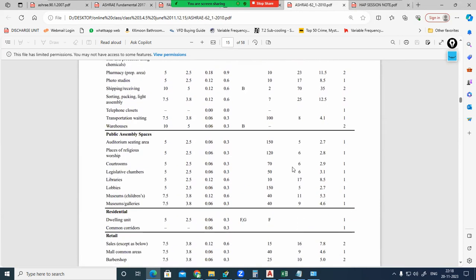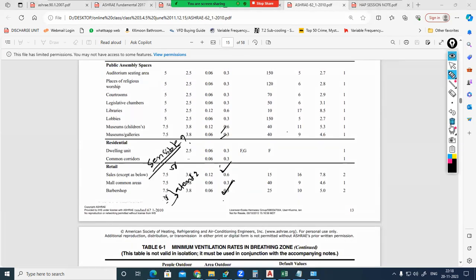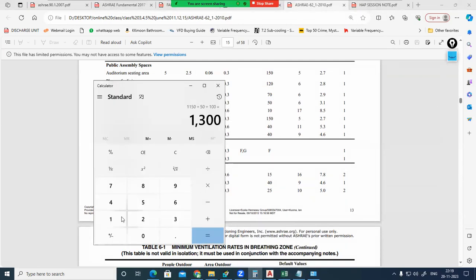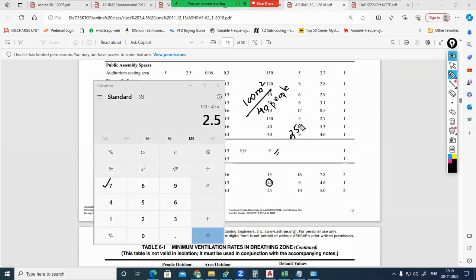So the meter square per person value we can find from here. For example, when you're designing a mall common area, 100 meter square of floor area will have 40 people. That means 100 divided by 40, how much will it come? 2.5, right. 2.5 meter square per person. From the occupant density, the meter square requirement per person we can calculate. Area requirement of one person, 2.5 meter square.